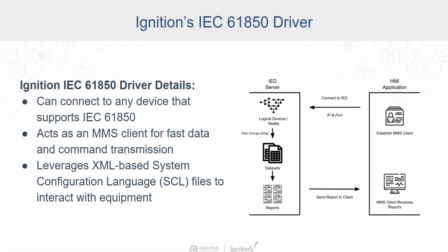Simple to use and requiring little to no knowledge of 61850 standards, the driver acts as an MMS client, allowing acquisition of status and measurement data by either polling or MMS reports. And those MMS reports are really important, as well as executing control operations using the control model defined by IEC 61850. MMS provides fast transmission of substation events, such as commands and reporting schemes, to effectively automate operations.